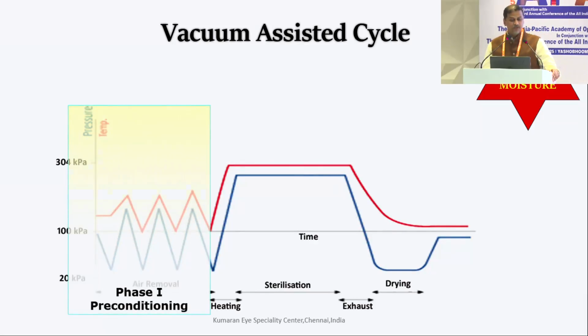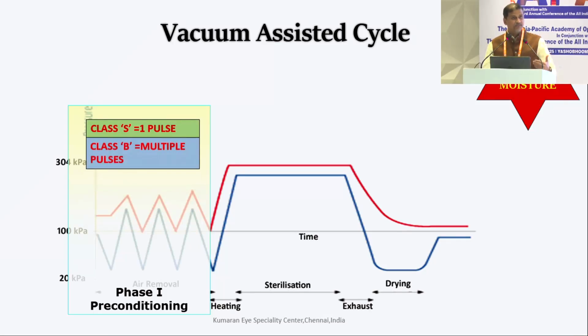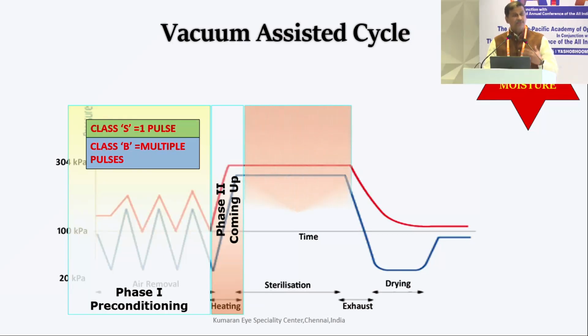So phase 1 is preconditioning. What happens in a class S autoclave is that there's only 1 pulse, so the vacuum pump takes the air out only once. But in class B, this spike is multiple times, so the pump works multiple times to take the air out. So this is the basic difference between an S and a B autoclave. Then you have phase 2 coming up, where the temperature keeps on rising. Then this steam is let into the main chamber, where the time depending upon your load is maintained.